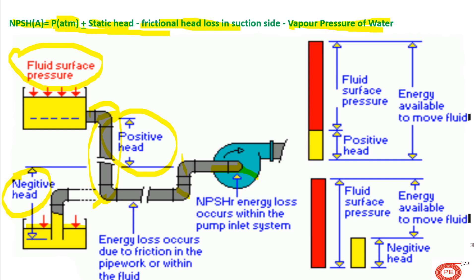Vapor pressure depends upon the properties of the liquid. If pumping a liquid at 20°C, vapor pressure will be less; if pumping a liquid at 500°C, vapor pressure will be more. As temperature increases, vapor pressure also increases, and as this value becomes larger, the NPSH available calculation becomes smaller. So while calculating NPSHA, make sure you know the vapor pressure and the temperature of the liquid being pumped.